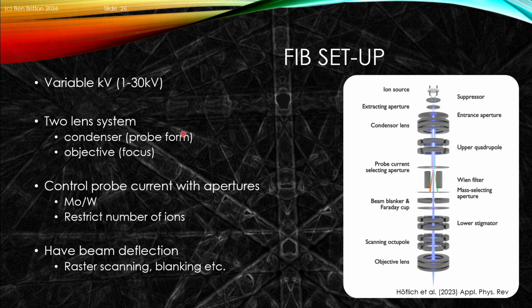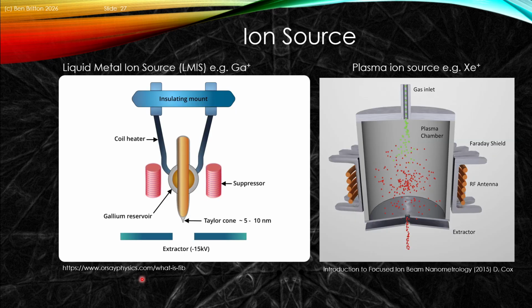So we have this overall system that I mentioned a couple of times now, but one of the important aspects is that we're going to control the probe current, typically with apertures. Those apertures are often, say, molybdenum or tungsten. These are radiation hard materials that don't sputter very quickly, because all the ions that don't go down the column will interact and hopefully be quenched or stopped by the aperture itself. And again, we'll have beam deflection, raster scanning, blanking, etc. to enable us to maximize the use of the FIB for the applications that we're interested in.